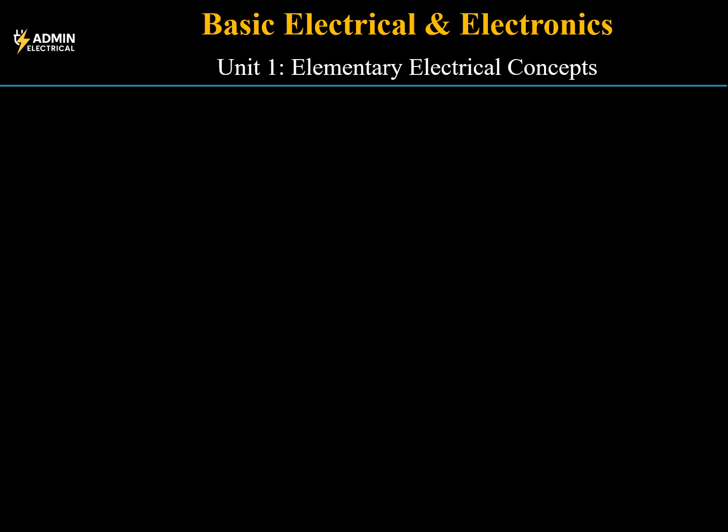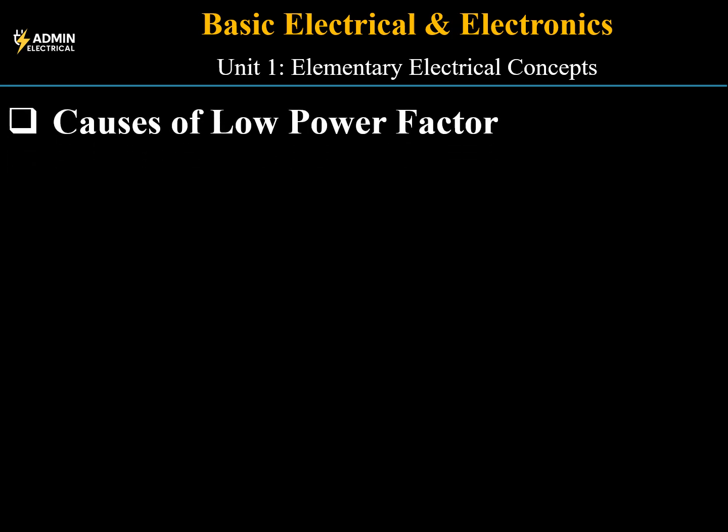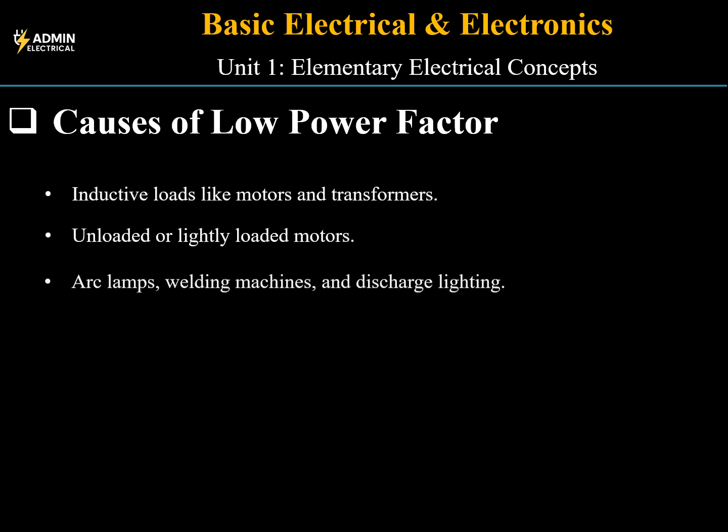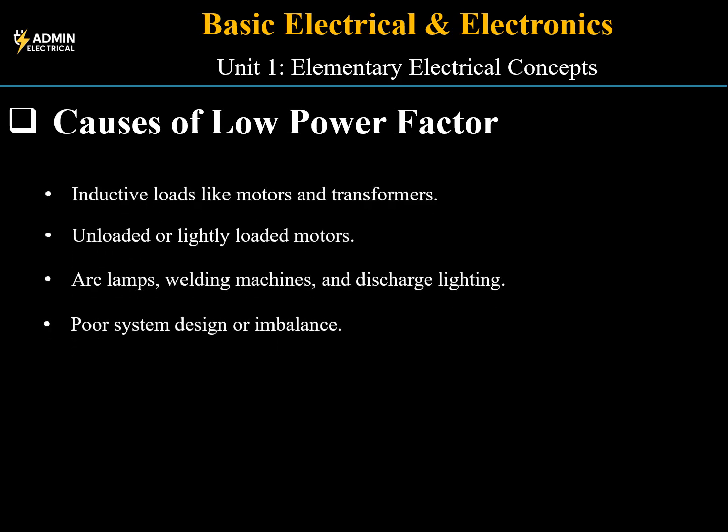There are many reasons why power factor becomes low. Inductive loads like motors and transformers, unloaded or lightly loaded motors, arc lamps, welding machines, and discharge lighting, poor system design or unbalanced loads, all these cause the current to lag behind the voltage, lowering the power factor.